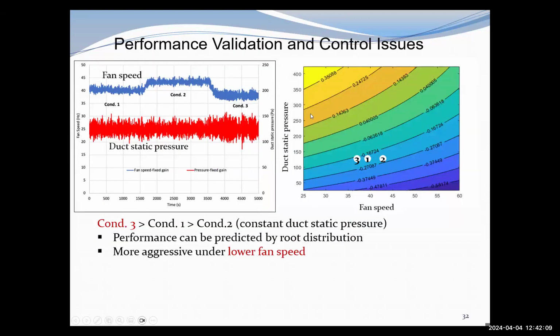So here for condition 1 to condition 3 with a constant duct static pressure, the right figure shows the corresponding pole locations and the left figure shows the test result. We can see under condition 3, with the lower fan speed, it has a more aggressive response here. And correspondingly in the root distribution at point 3, the real part has a smaller negative real part.